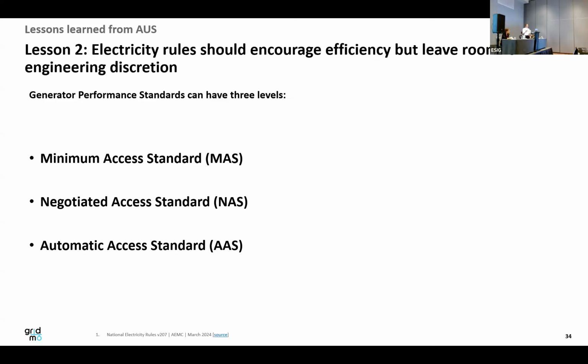Plucking an example here, from talking to some people at the conference: what's the reactive power capability that you need to provide as a generating system? This is one of the clauses. If you're a 100 megawatt solar farm, is the Q you're providing 20 megawatt, 30, 40? That can be a detailed assessment, but the automatic access standard is 39.5 megawatt. One of the lessons learned was that the time you could spend debating whether 39.5 or 34.5 or 36.8 is the right number is probably not worth it, compared to just adding another inverter.